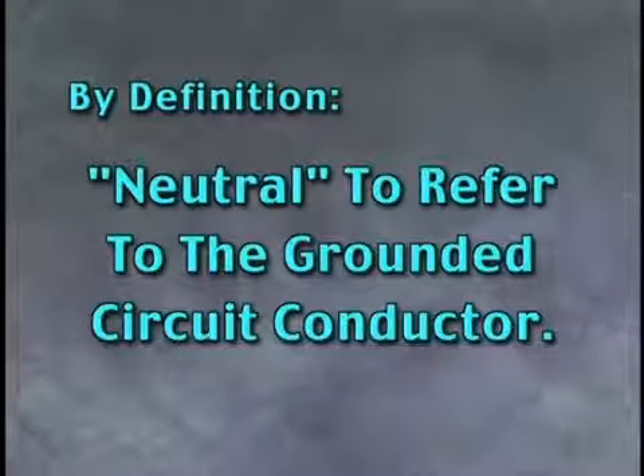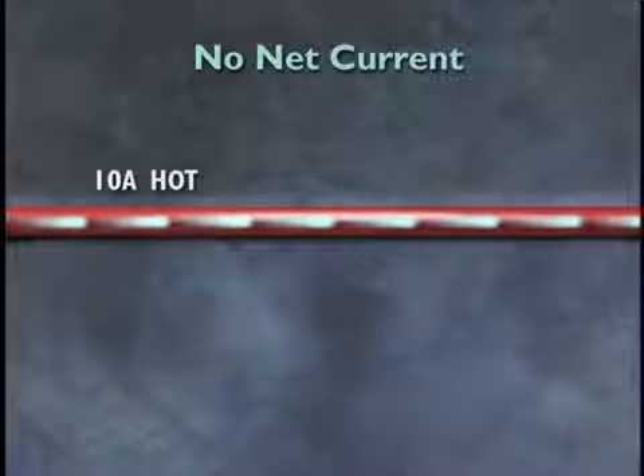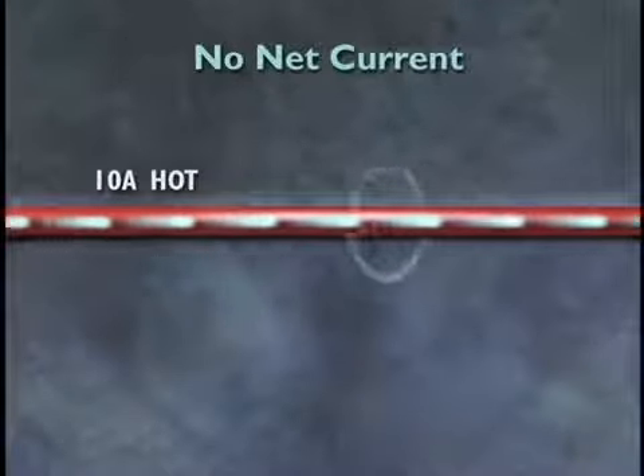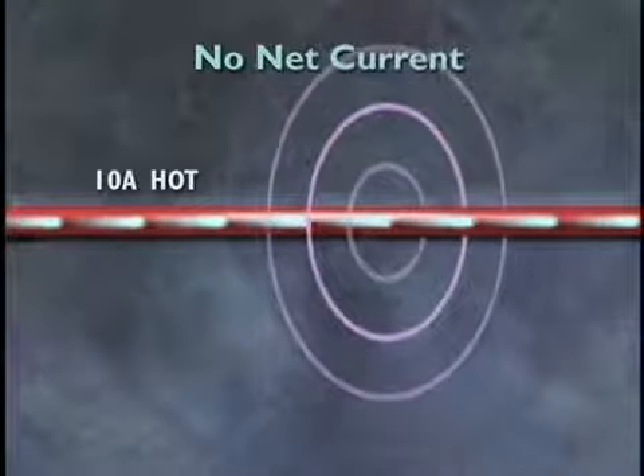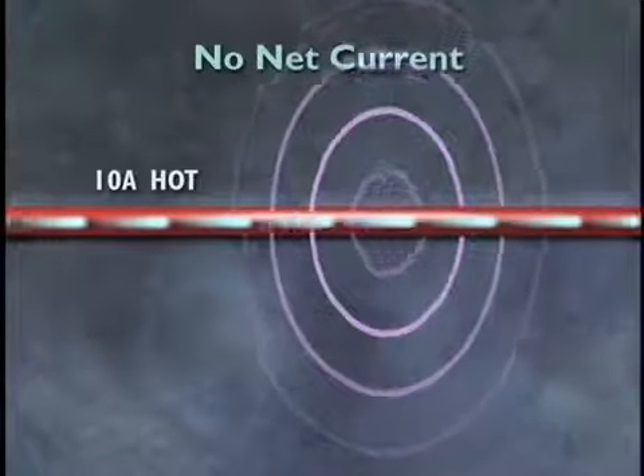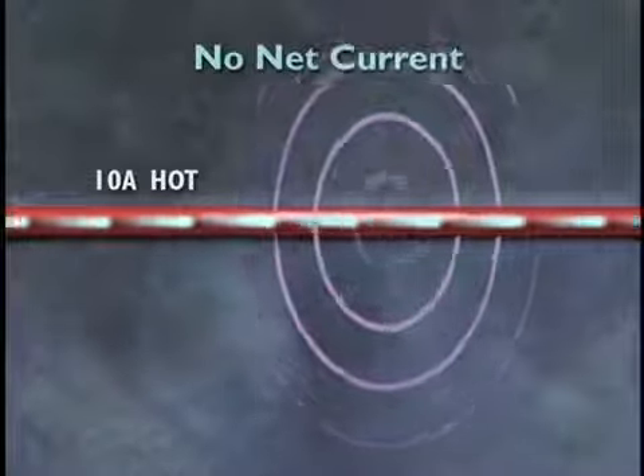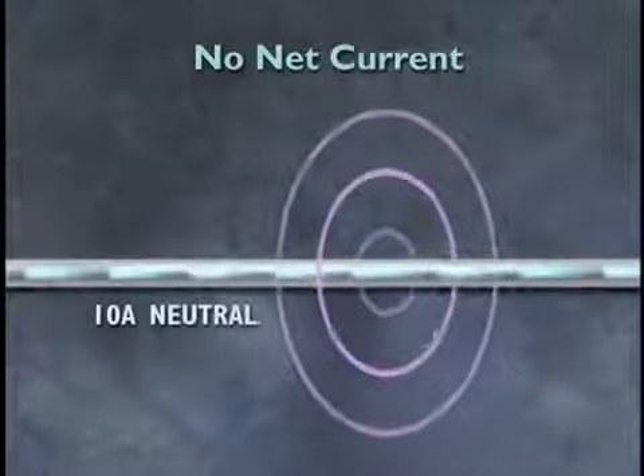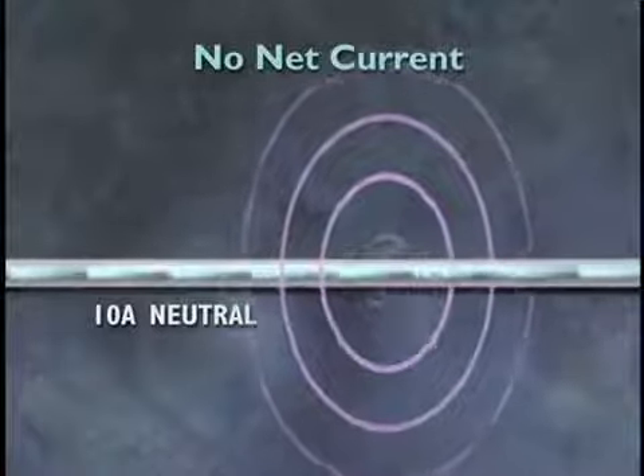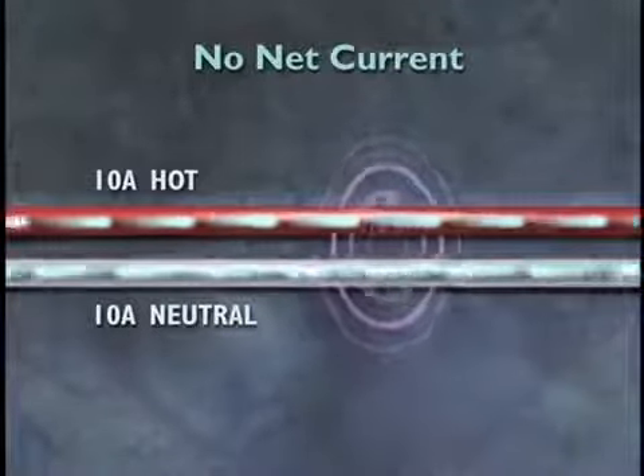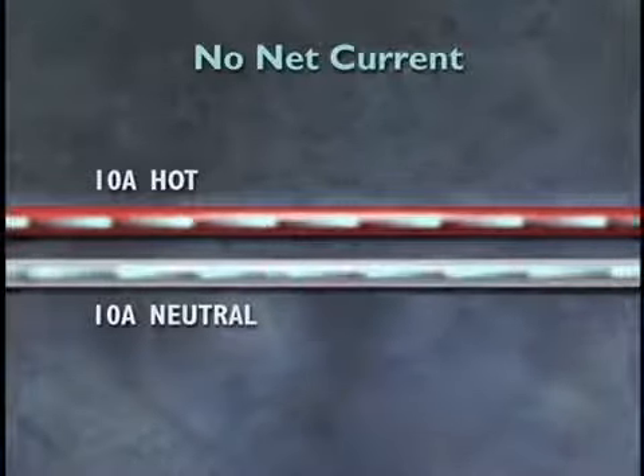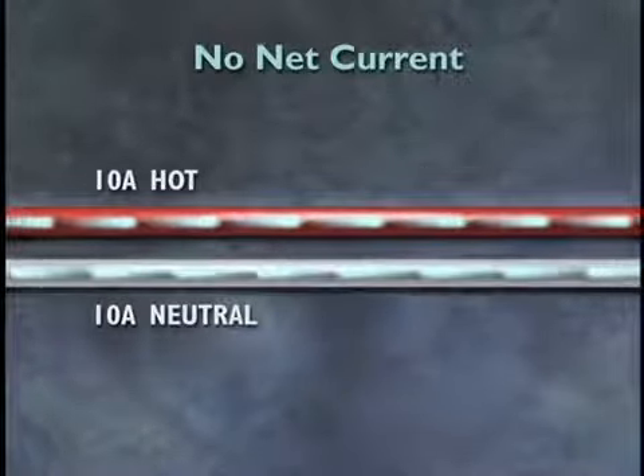There is both a theoretical and practical definition of a net current. In this video, we will use the word neutral to refer to the grounded circuit conductor by common usage. When a wire conducts current, a magnetic field is created around the wire. The strength of the field is proportional to the amount of current, or amps, flowing through the wire. In this example, the hot leg carries 10 amps. In a normal circuit, the neutral leg also carries 10 amps. The net current here is 0, because both legs conduct the same amount of current, but in opposite directions.